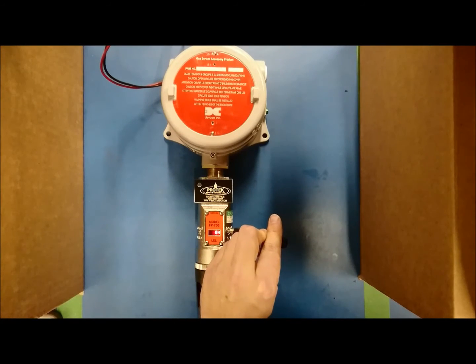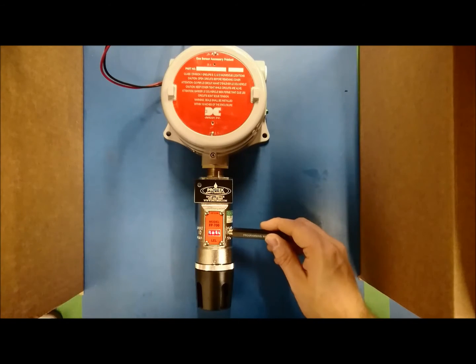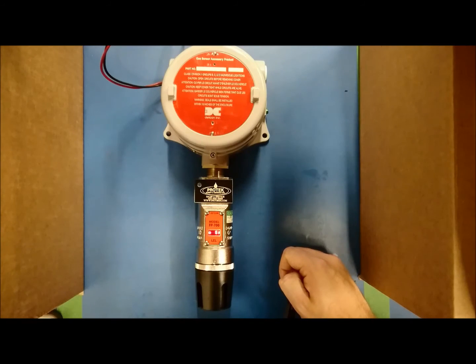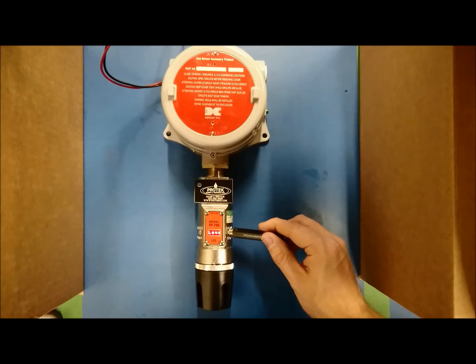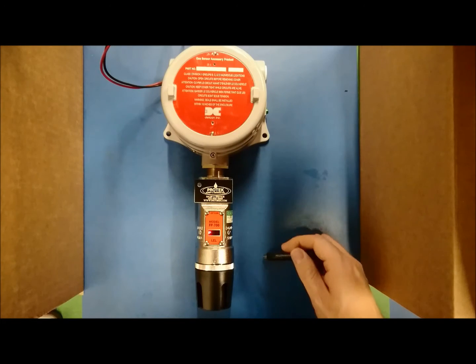The display will read 'view sensor status' across the screen. Hold the magnet over PGM2 until an arrow pointing right appears, then immediately remove the magnet. The display will read 'set autospan level.' Hold your magnet over PGM2 until an arrow pointing right appears, then immediately remove the magnet.